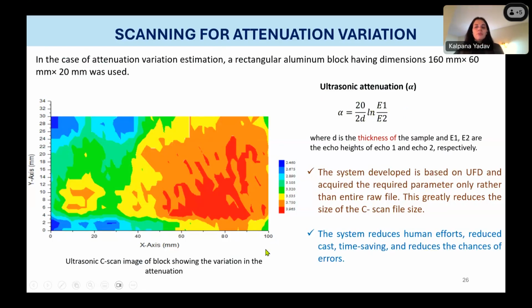So the system developed is based on UFD and acquires only the required parameters rather than the entire raw file. You don't need to have all the data. You acquire only the data you're interested in. And this greatly reduces the size of the C-scan files. Basically, when you do a lot of testing, these files are in the gigabytes. To avoid that, you need a data acquisition card that has a better sampling rate, like 250 or something. So this automation system also reduces those limitations, reduces human effort and human errors, reduces cost, saves time, and there are fewer chances of error.